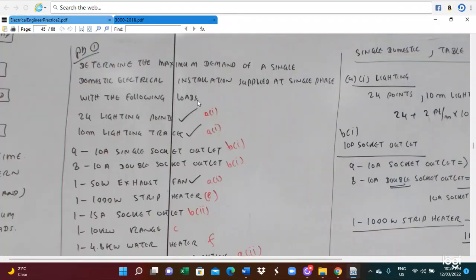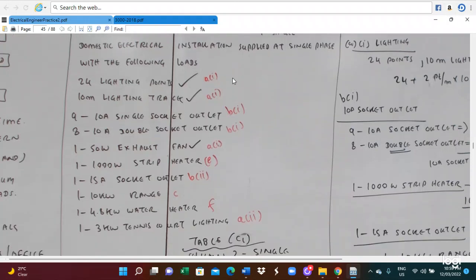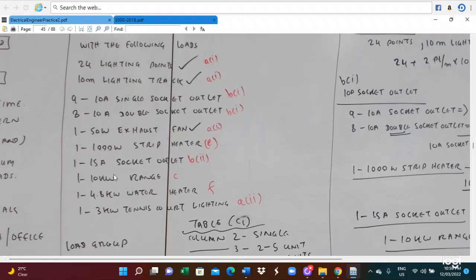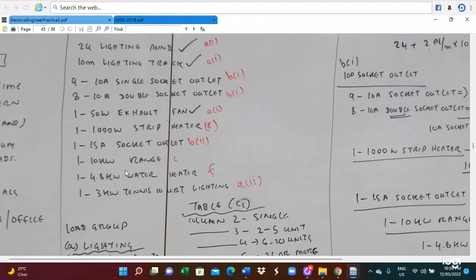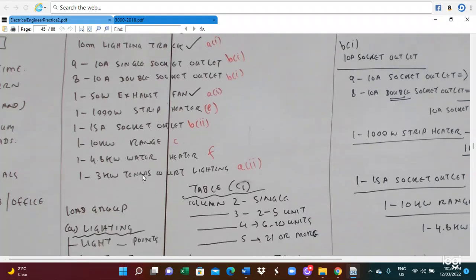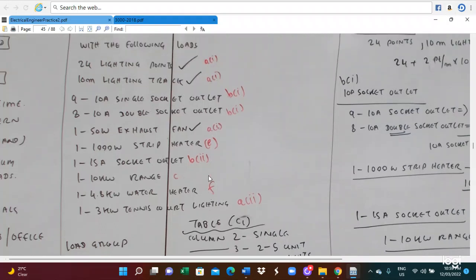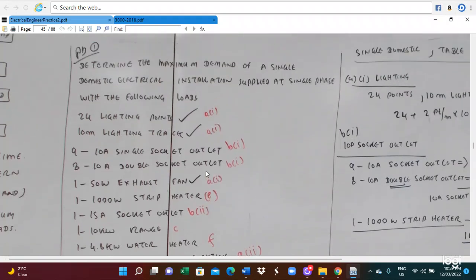Determine the maximum demand of a single domestic electrical installation supplied at single phase. It includes 24 lighting points and 10 meters of lighting track, 9 numbers of 10 ampere single socket outlets, 8 numbers of 10 ampere double socket outlets, 1 number of 50 watt exhaust fan, 1 number of 1000 watt heater, 1 number of 15 ampere socket outlet, 1 number of 10 kilowatt range, 1 number of 4.8 kilowatt water heater, and 1 number of 3 kilowatt tennis court lighting. So those are the electrical loads provided.